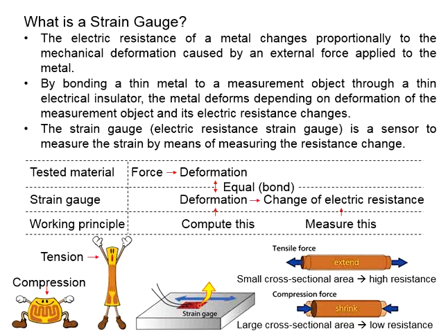It is only when the deformations of the strain gauge are the same as the deformations of the material that the reading given by the strain gauge shall be considered the deformations of the material. Since the whole thing here is based on electric current, the materials that you are measuring may also conduct current. This is going to affect the results in the strain gauge.